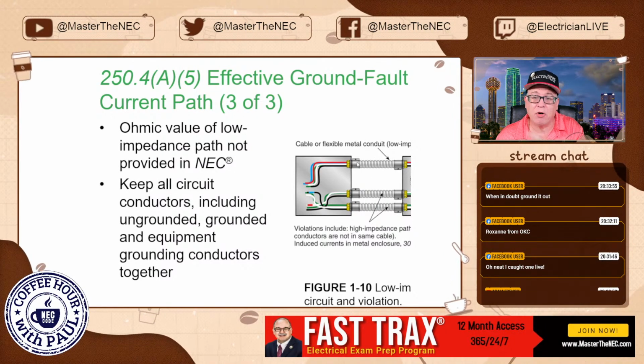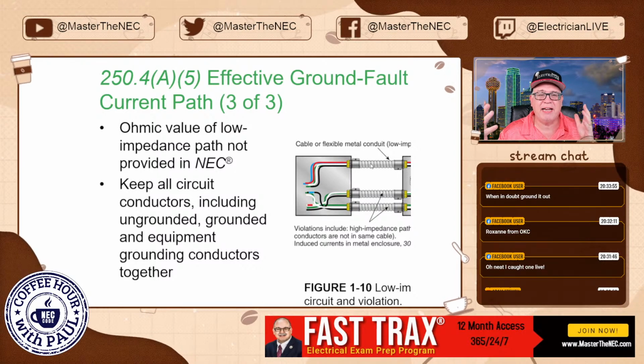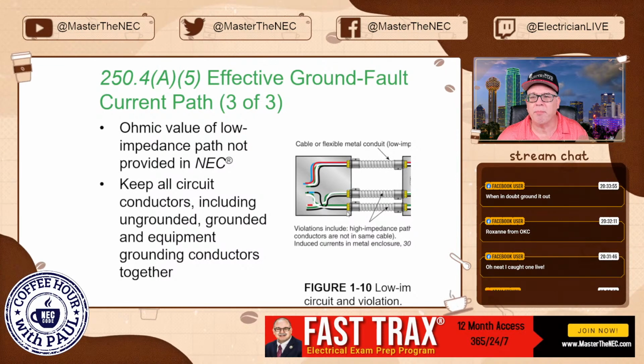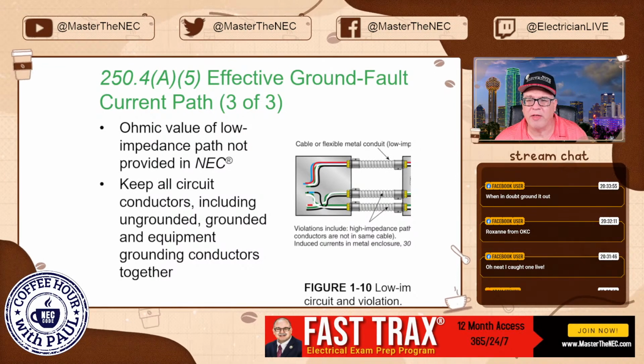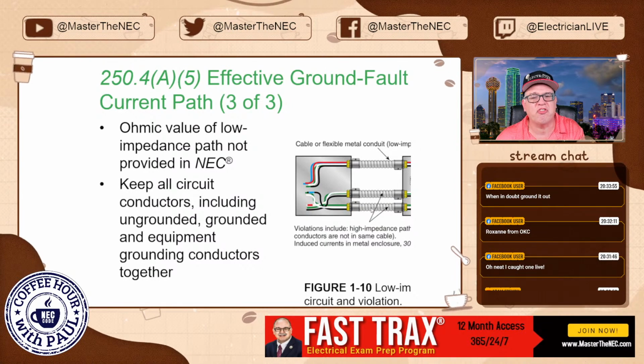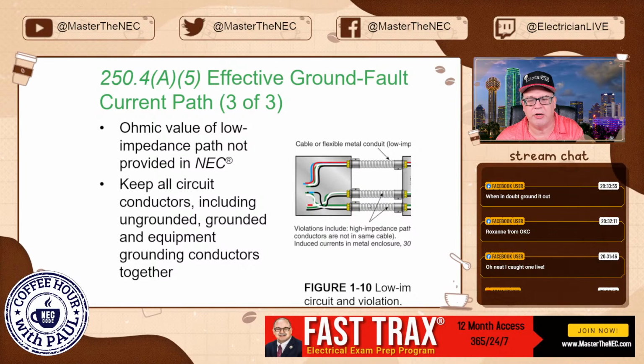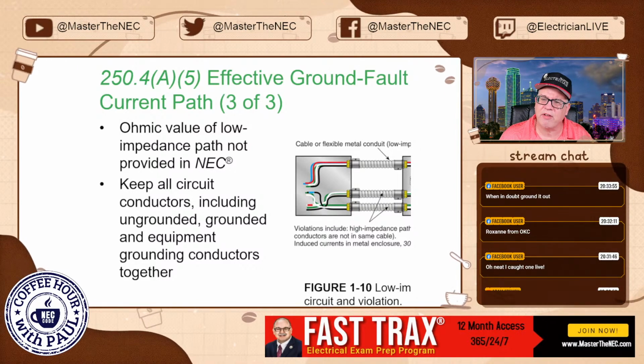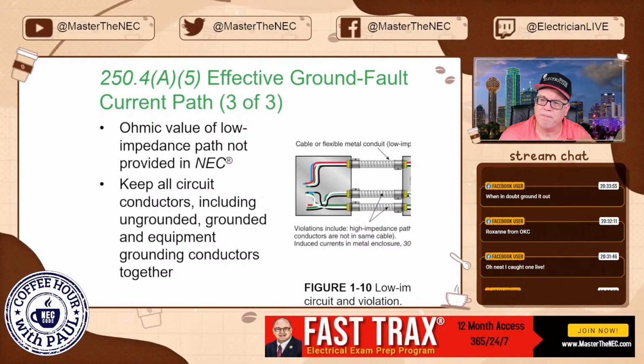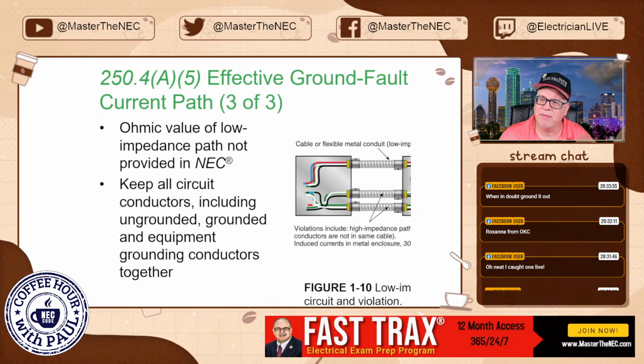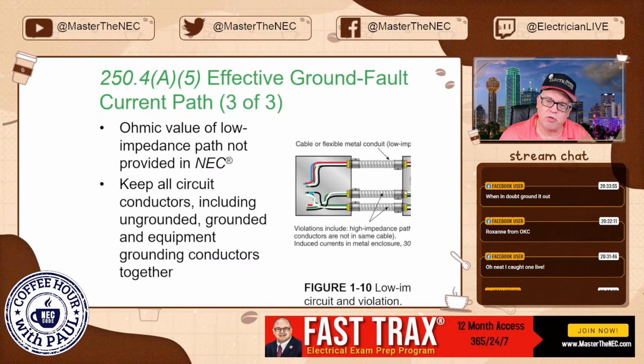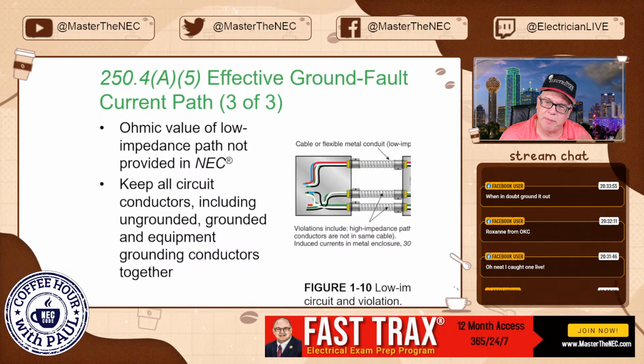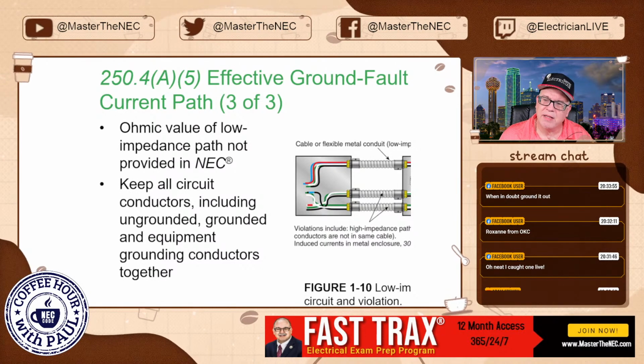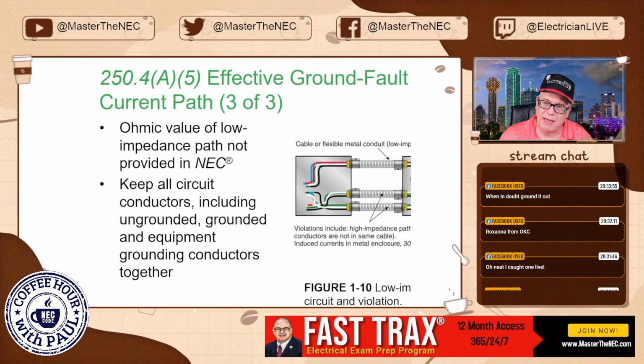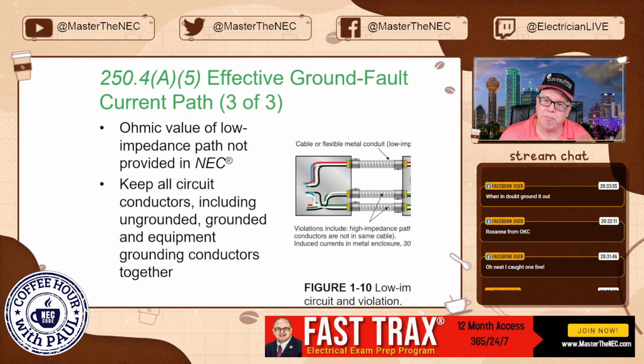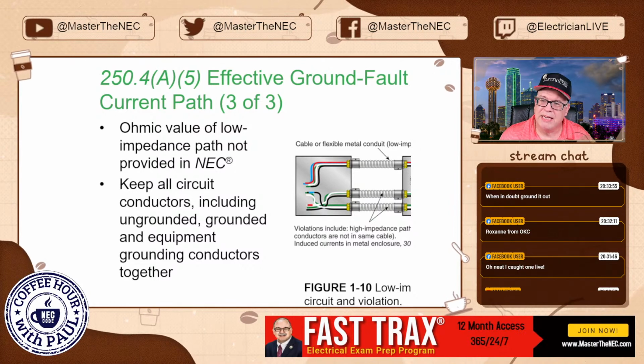Now, down here, and of course, you don't have any issue of high impedance here because of separating the circuits. Well, down here, this was an improperly devised system. So they needed to run it, so what they did was, instead, they ran two separate cables. Or in this case, I guess it's FMC, so it's conduit. Ran two separate ones. And in this raceway right here, they put the neutral and they put the black and the equipment ground. And in this one, and actually, no, it isn't neutral. Actually, this is one of the phases. So here it's black, red, blue. Here it's black and they used the white, and they re-identified it as red, okay? And then down here, they put the blue, which was black, and re-identified it as blue, and then ran the neutral down here.